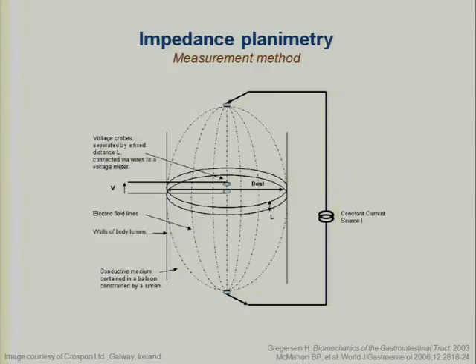In a nutshell, it's a method where there are 2 impedance electrodes that are encased inside of a balloon. Inside of the balloon there's also a conductive liquid, and when a steady current is being applied to the impedance electrodes, the voltage between them can be measured, and the changes in the voltage are reflective of the changing diameter of the balloon within. The voltage is inversely proportional to the cross-sectional area where the 2 electrodes are. As you can imagine, once you stack those electrodes on top of each other, what you can create is a 3-dimensional image of any lumen that you put the balloon into.